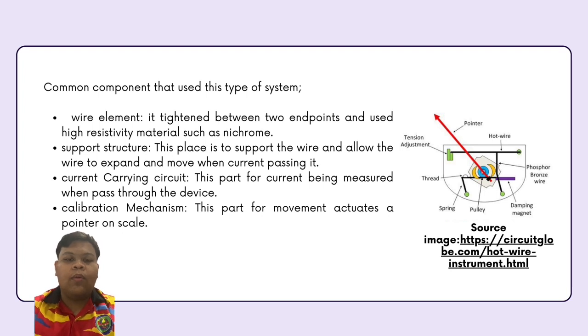There are 4 components that are usually used for a hot wire type system. The first one is the wire element. This wire element is tightened between 2 endpoints and a high resistivity material is used, such as nichrome. Secondly is the support structure. This is to support the wire and allow the wire to expand and move when current passes through it.